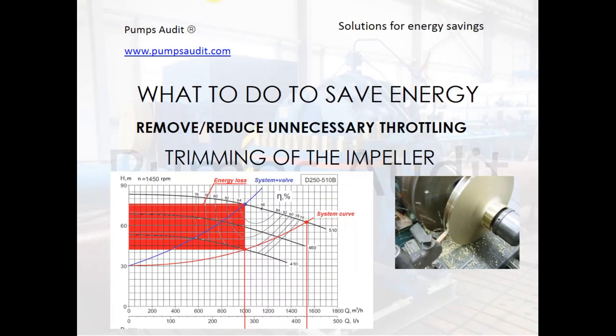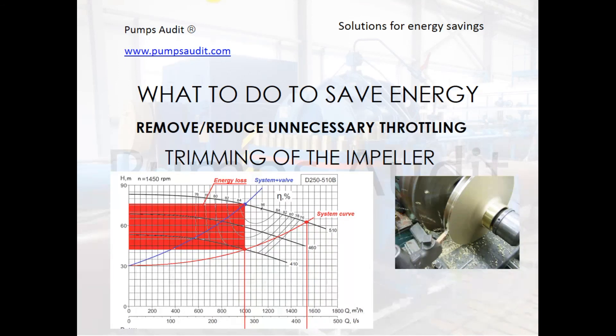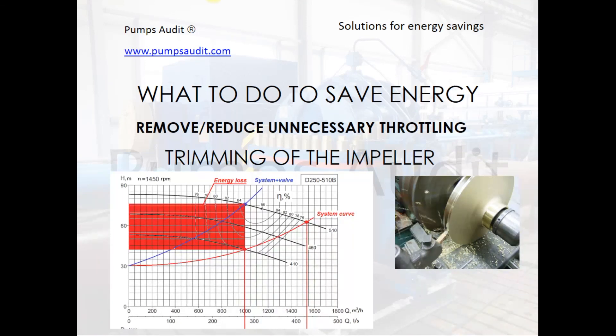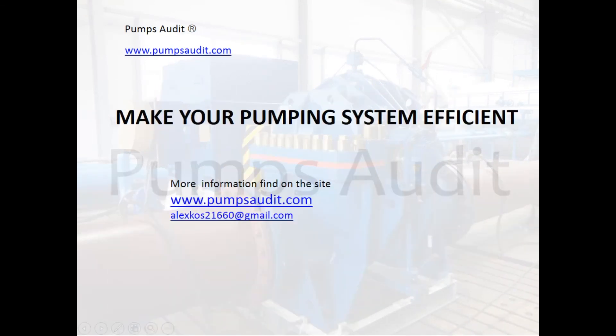Trimming the pump impeller is a very effective method of energy saving. It is applicable in systems with a stable characteristic over time, where it is clear that the pump is oversized. It can give up to 20% energy saving. Make your pumping system efficient.